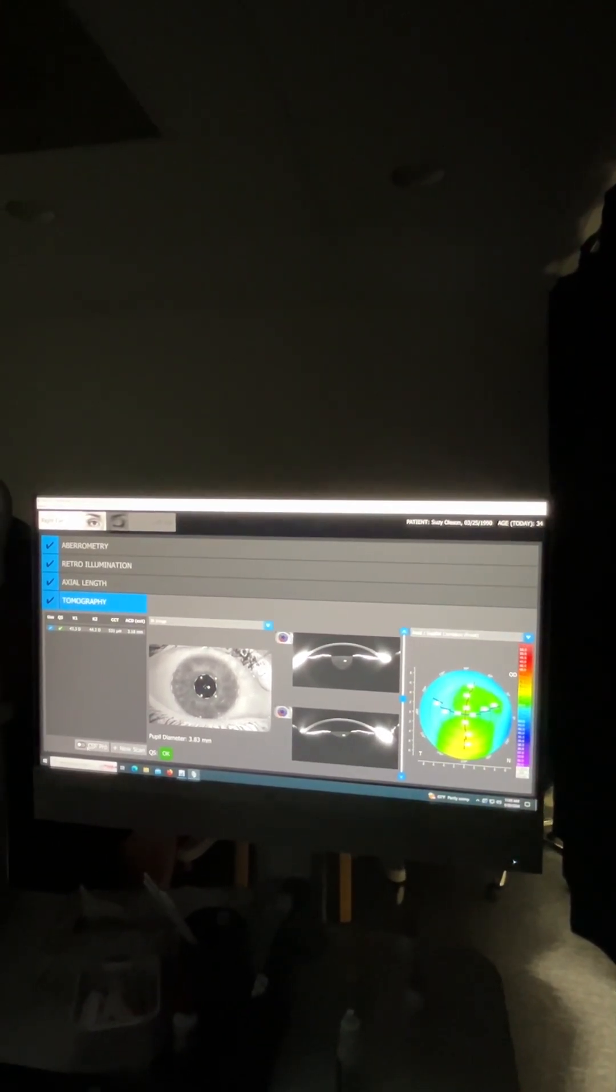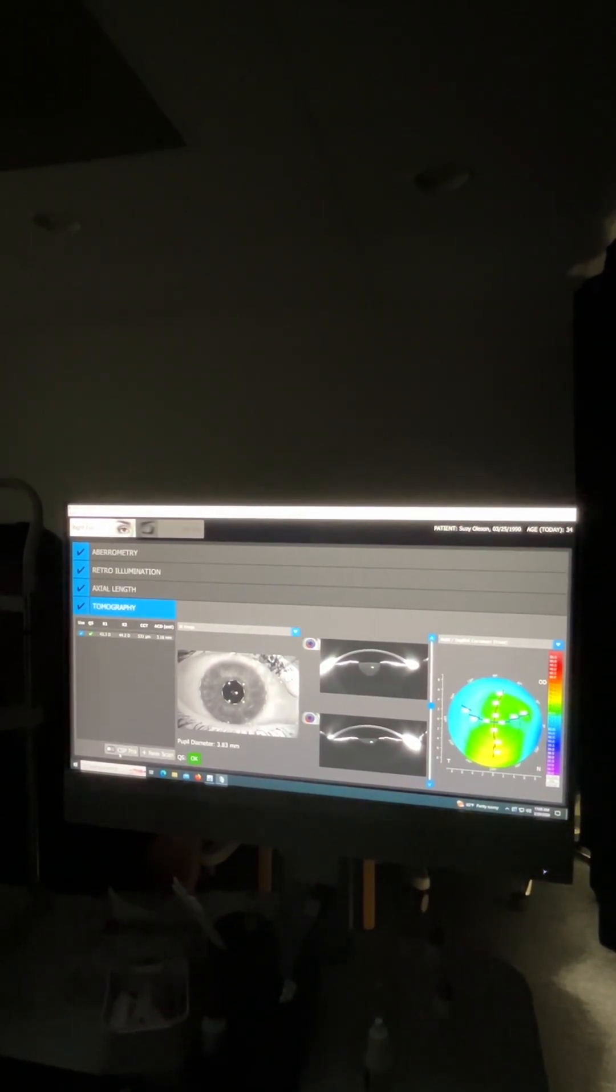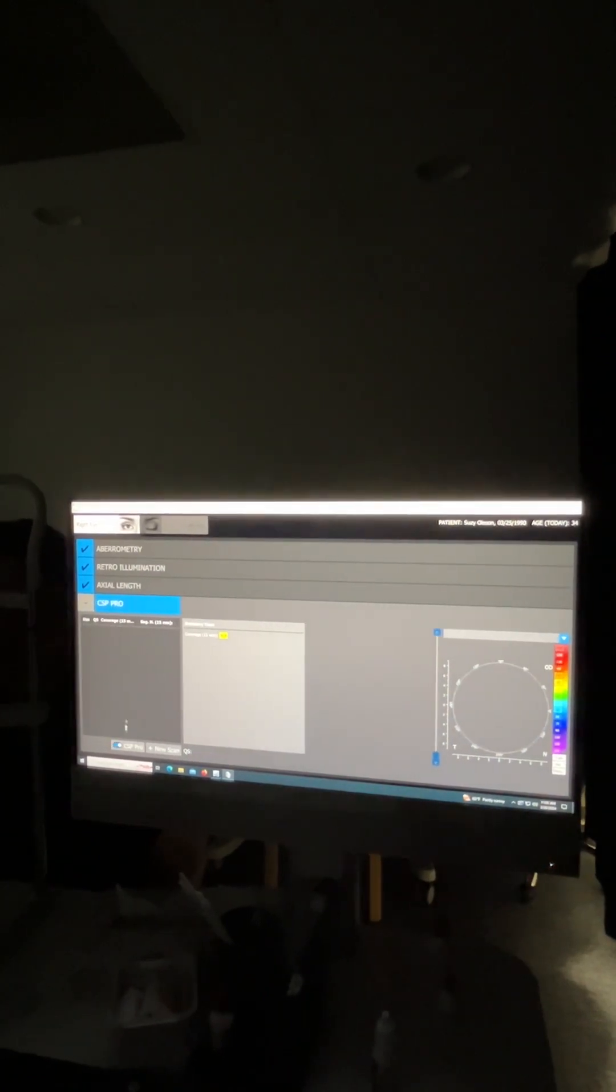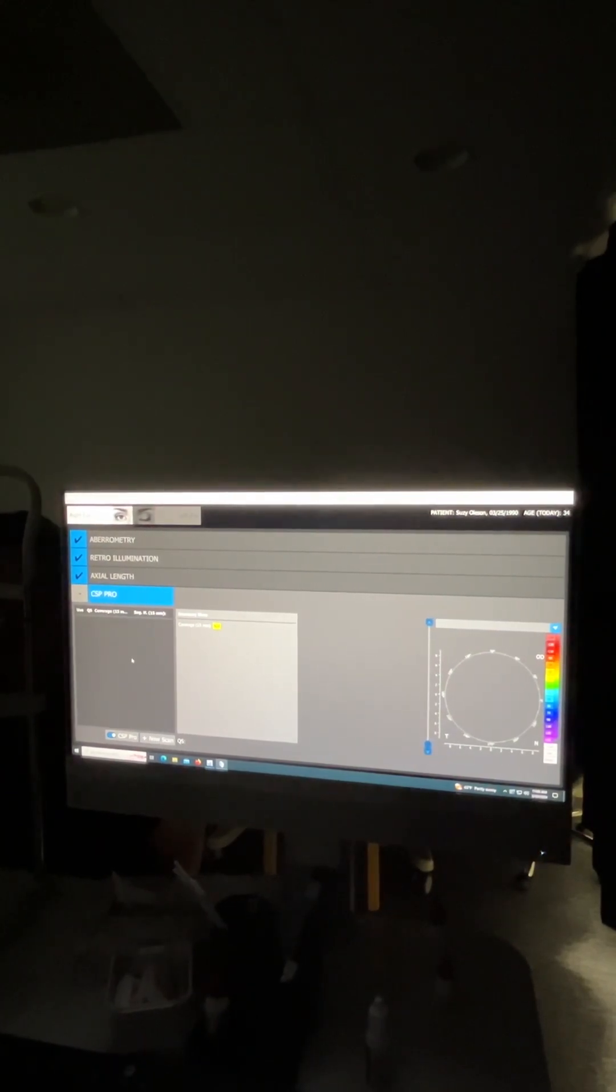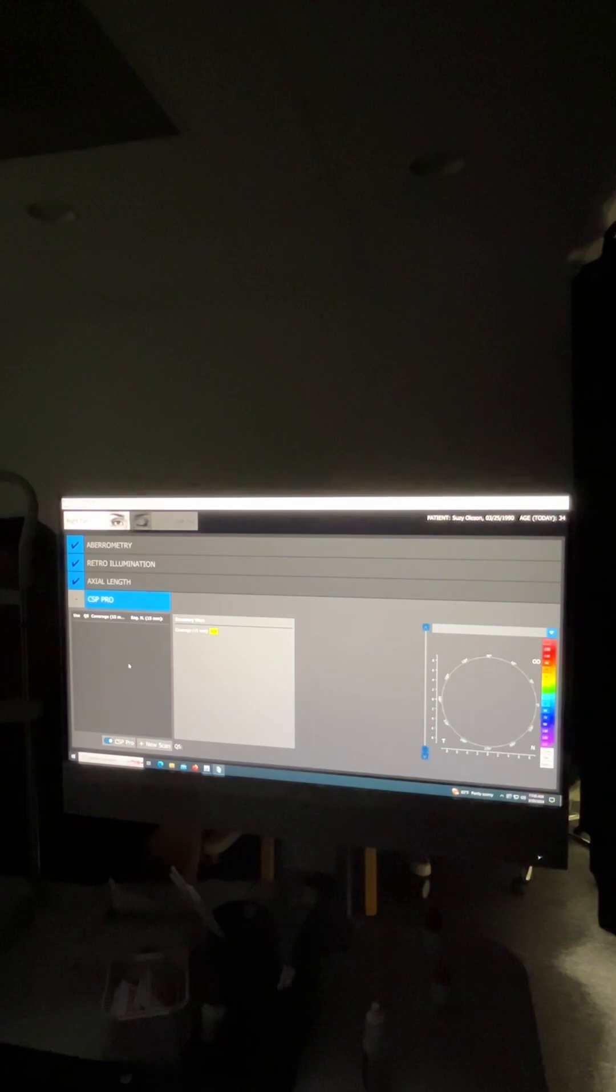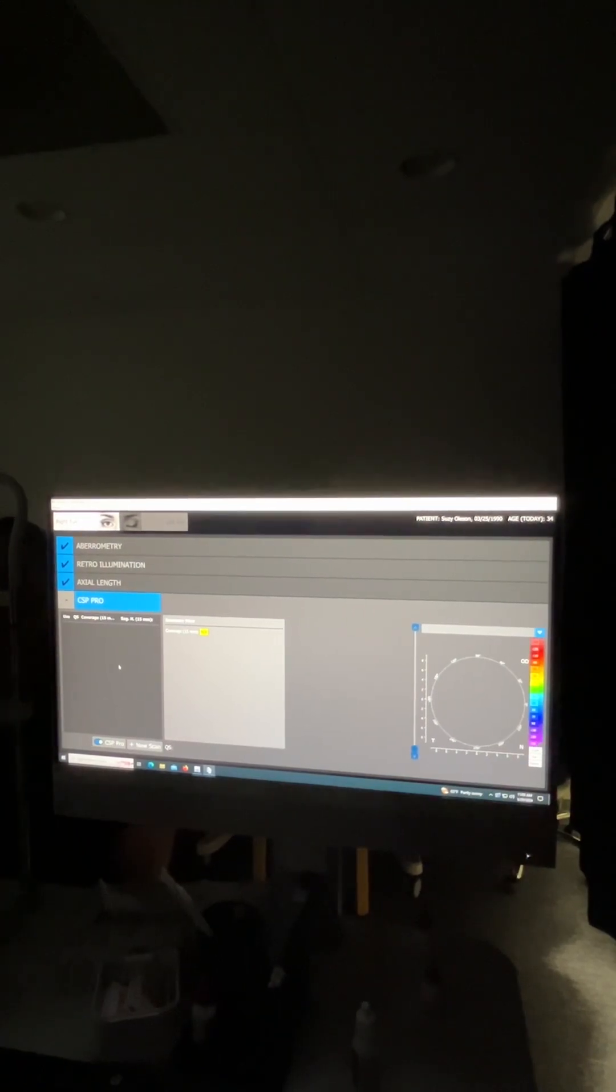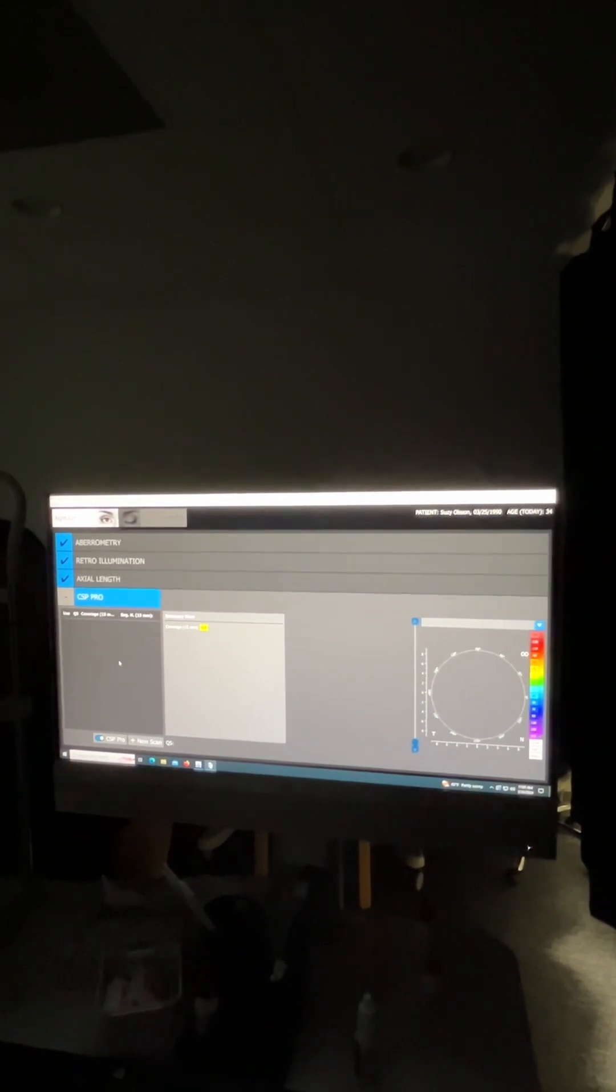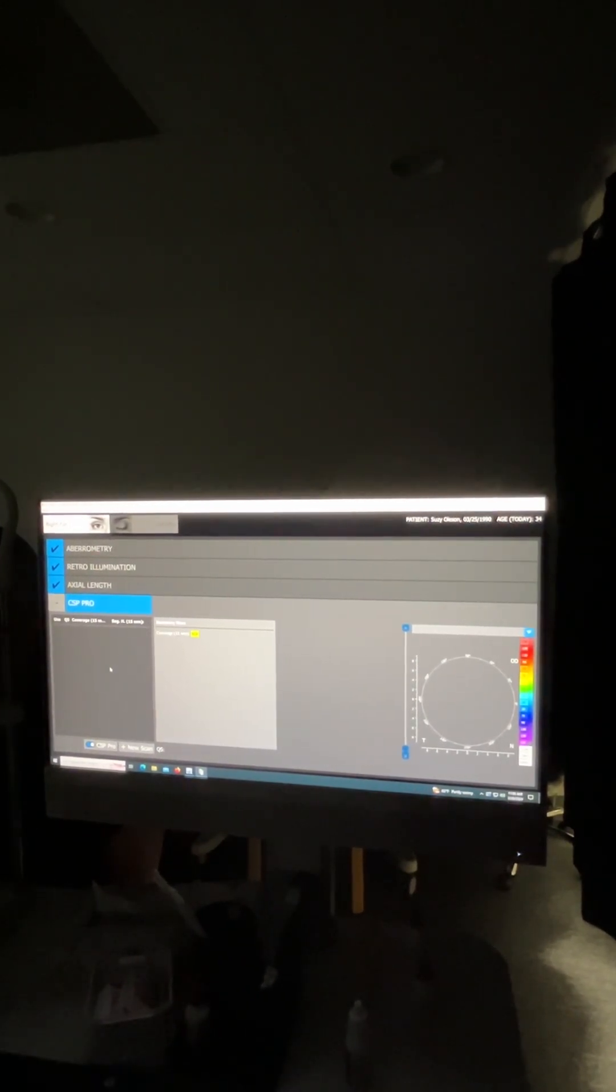There's also another feature in tomography. It's called CSP Pro. CSP stands for corneoscleral profilometry. And then some models of Pentacam will just have CSP, which is going to be five images taken separately, a central, top, bottom, side, and side. So five positions of gaze, and then the software will stitch it together. And this particular model, it takes a single shot. So that's the CSP Pro model. It will just take a single capture 18 millimeter image.